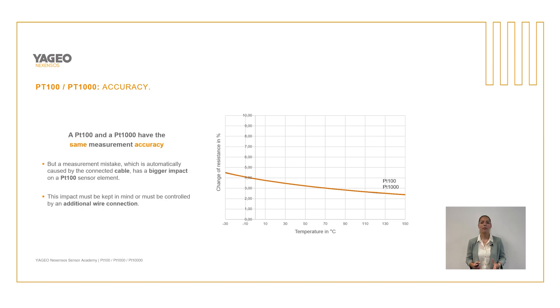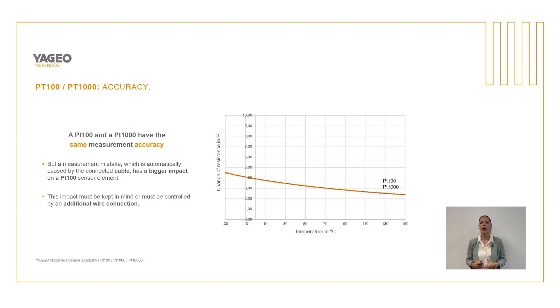However, a long cable lead can cause a measurement error. The length of the cable has a greater influence on the PT100 sensor, so accordingly, with a long cable, the PT1000 is preferred. Alternatively, a three- or four-wire connection can be used to minimize this influence.